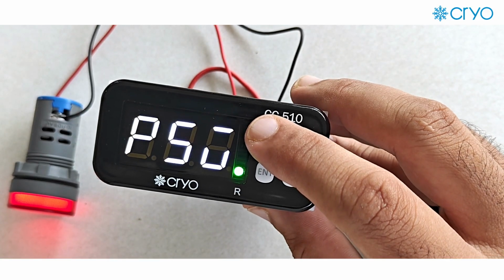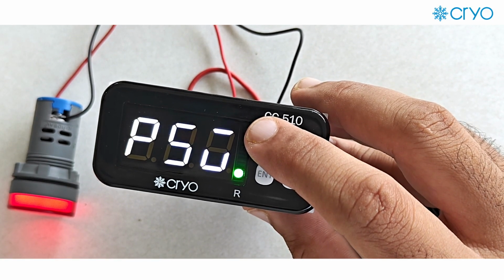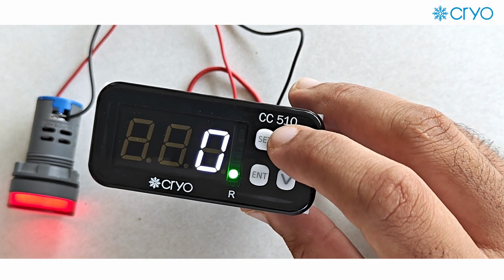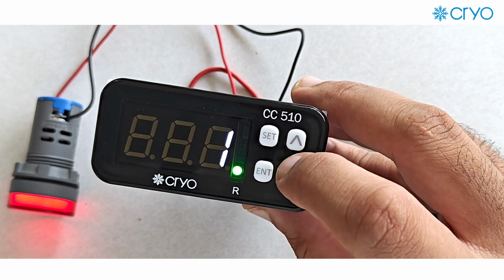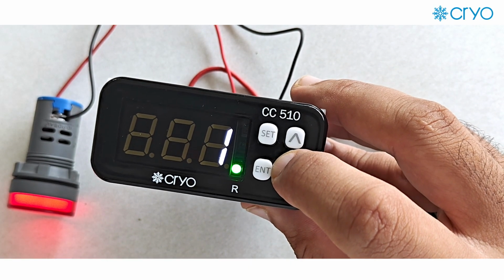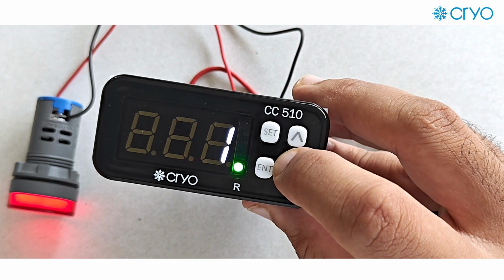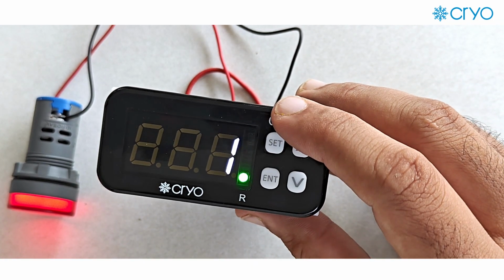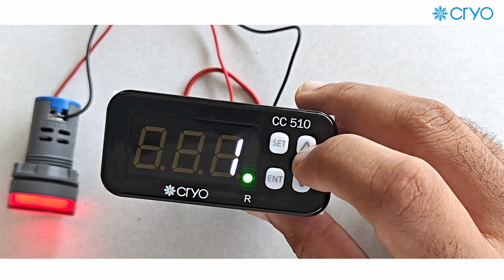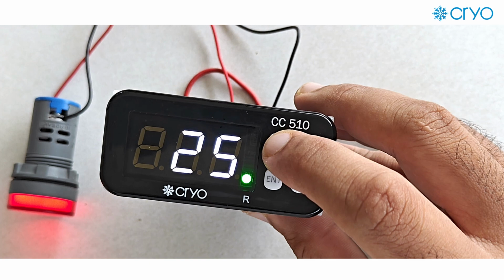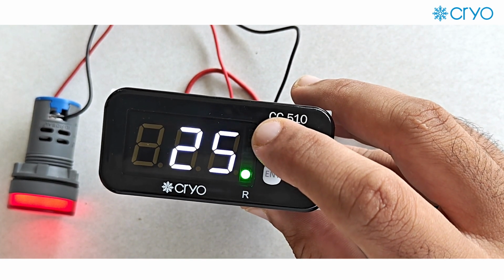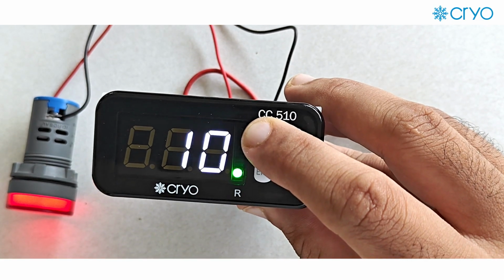If we again press the set button, the password will come on the display. This password option is to enable or disable the password. If you select 0, that means the password is disabled. If you select 1, that means the password is enabled. Each and every time you want to go into the parameter settings, one password page will open on the display, and the password for the controller is 39. If you enter 39 in the password and press the set button, then and only then can you go into the parameter settings. So again we have pressed the set button, and we have come out of the parameter menu.